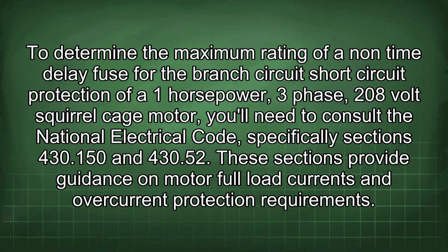To determine the maximum rating of a non-time delay fuse for the branch circuit short circuit protection of a 1 horsepower, 3-phase, 208-volt squirrel cage motor, you'll need to consult the National Electrical Code, specifically sections 430.150 and 430.52. These sections provide guidance on motor full load currents and overcurrent protection requirements.